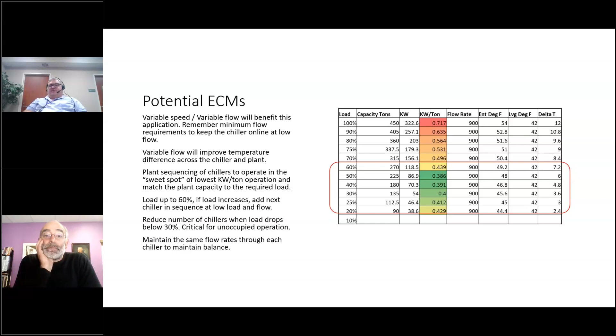Why would you want to run max flow rate at 20% load? But this is right out of the manufacturer, right off their cut sheet for the project. That's why I don't see them. It's rare that I see a variable flow performance on a chiller. I have to do that myself.